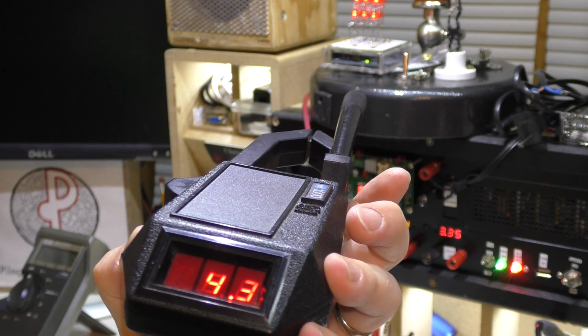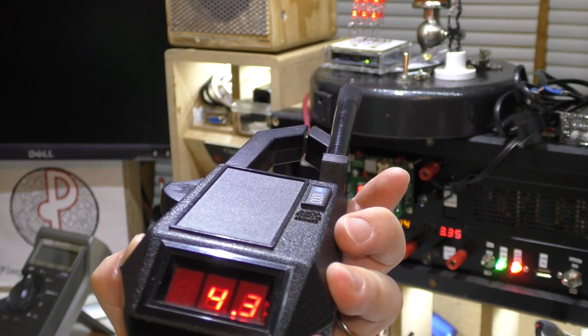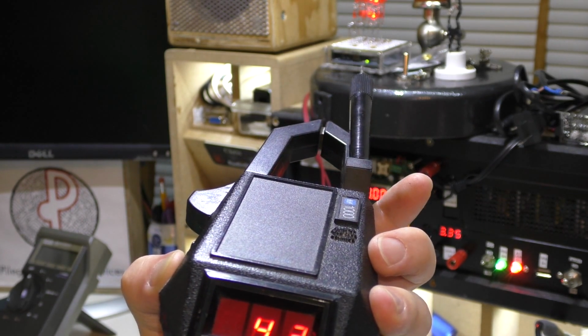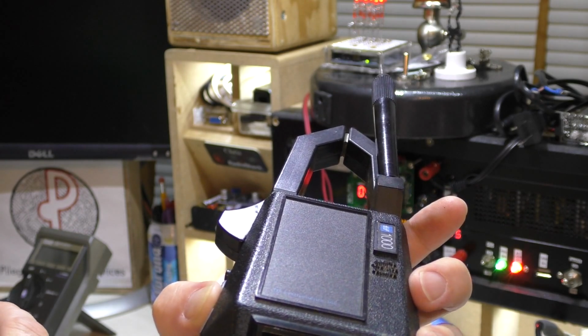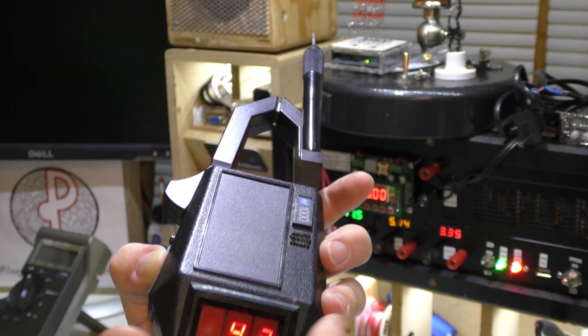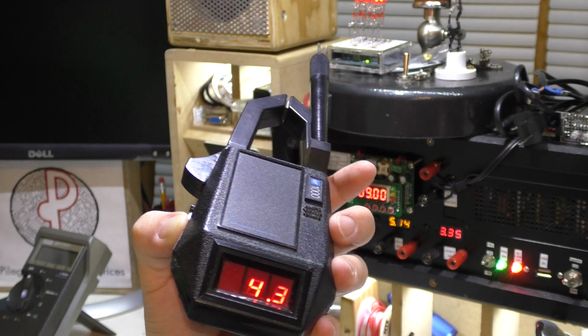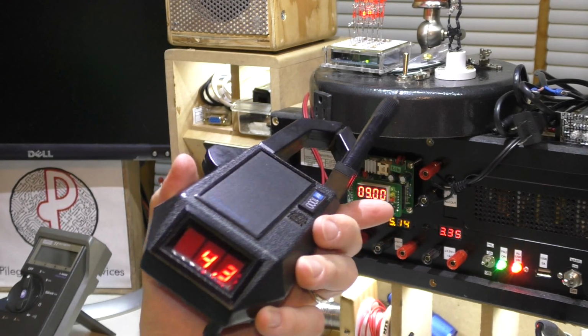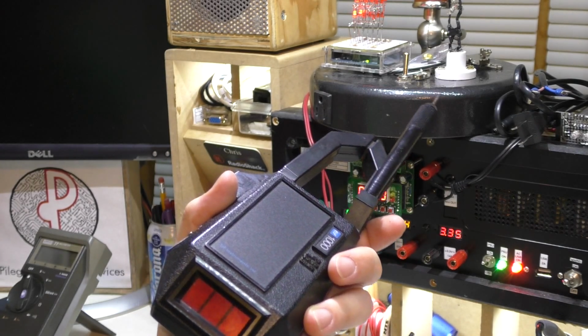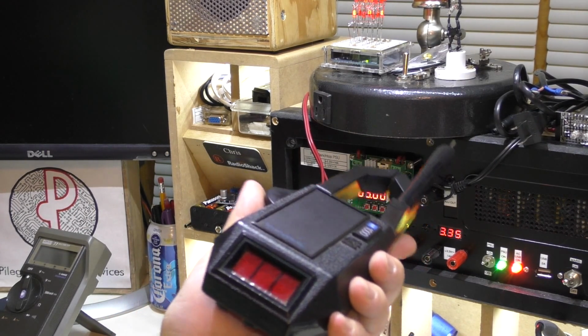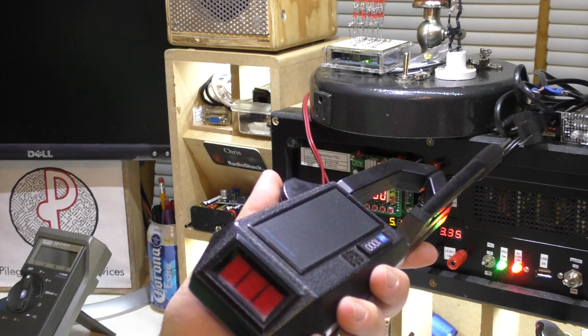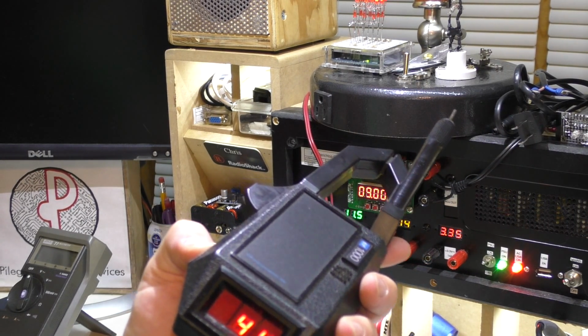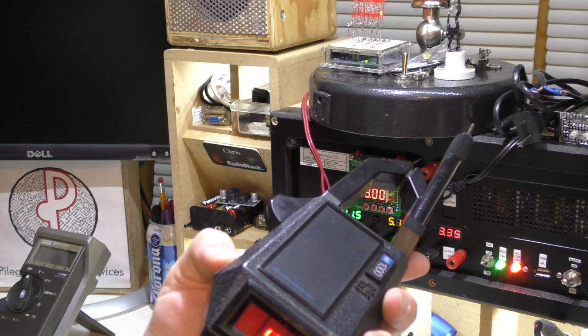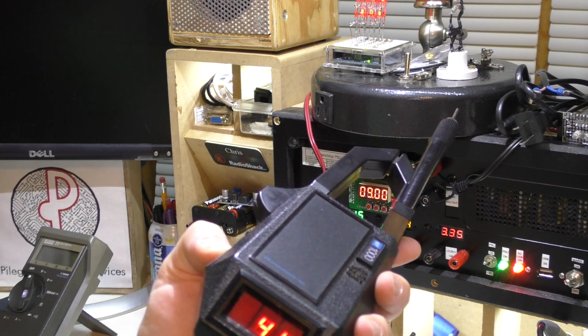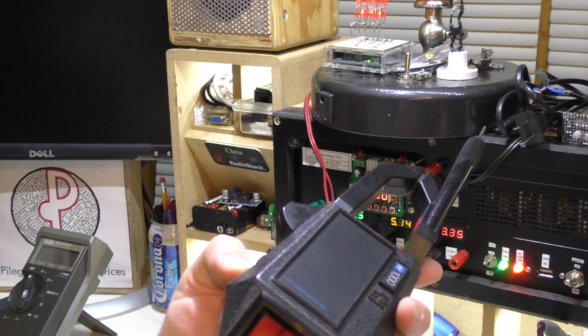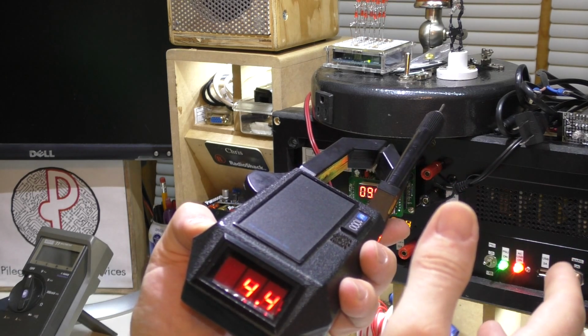When you hit the peak hold button, it will stay at whatever the highest peak is. This is useful when you want to see the starting load on something like a motor. One use would be finding the circuit feeding this room, clamping around the line, hitting peak, then turning the breaker on, so all the machines and computers that power up on their own will give me that peak amperage of everything starting up.